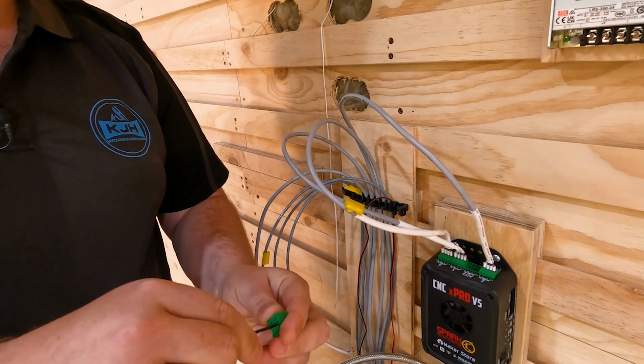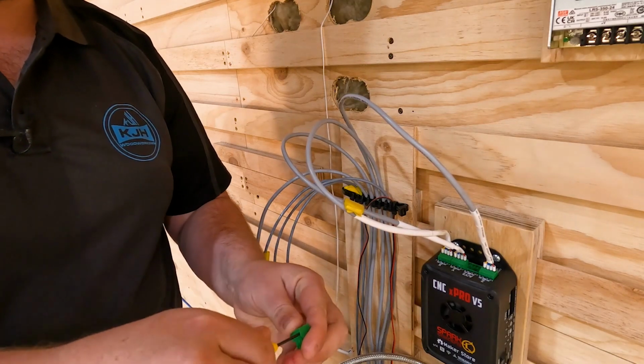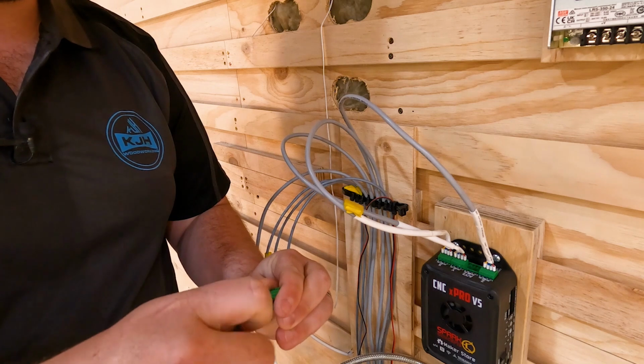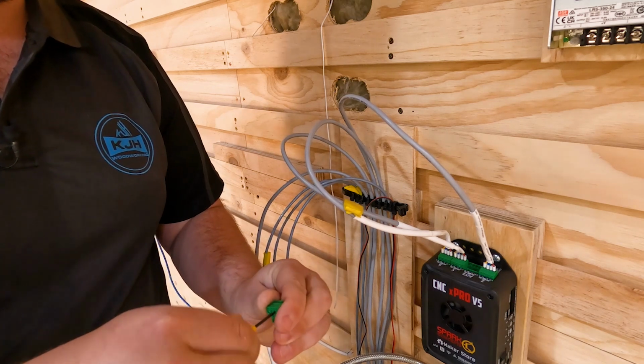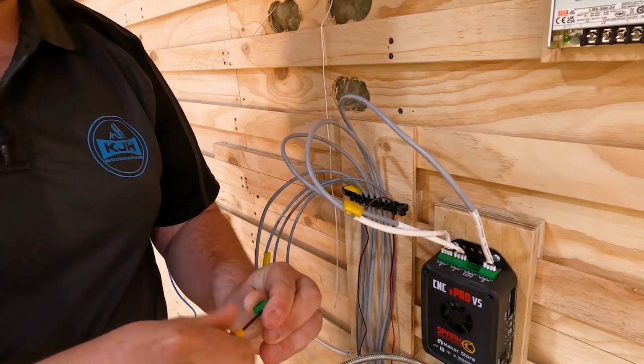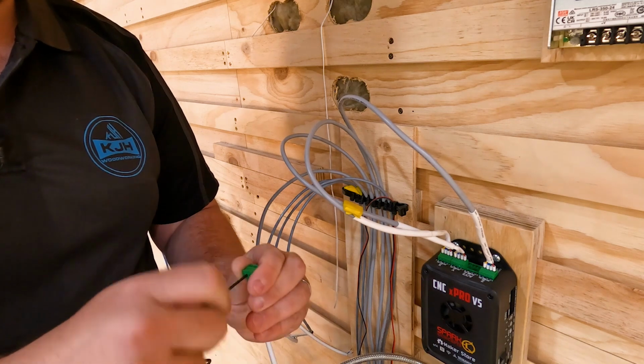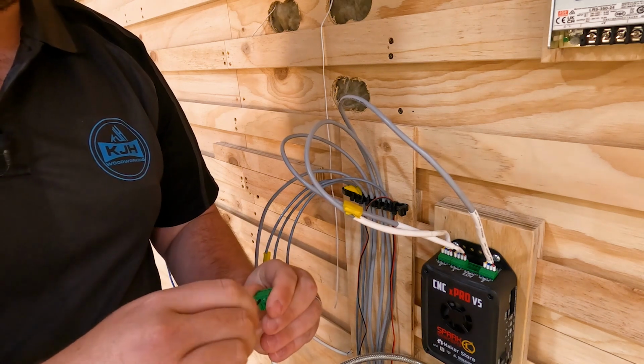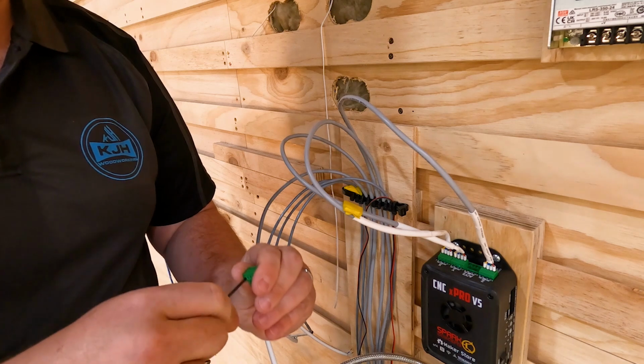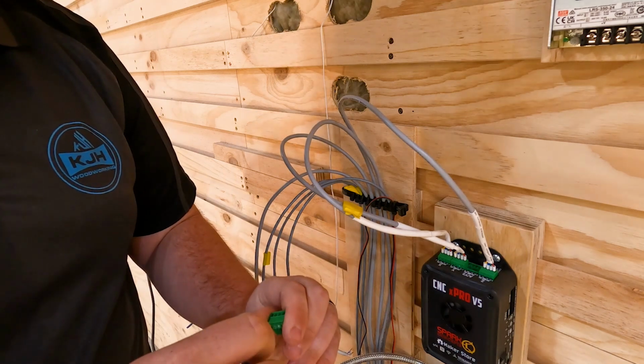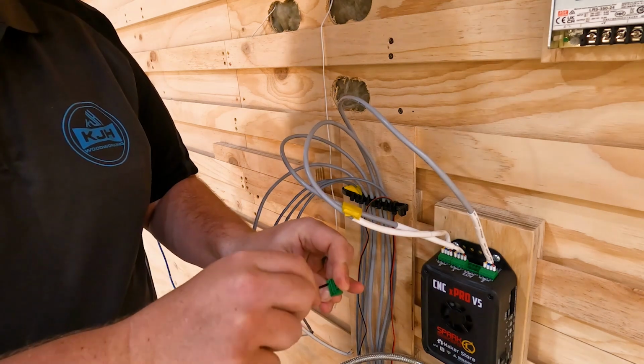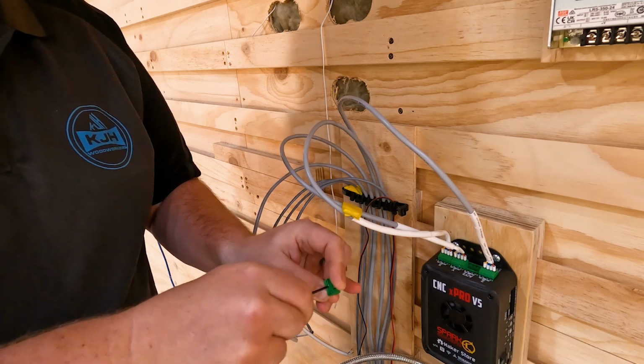For Y2, you need to reverse the colors at one end. I like to reverse it at the controller end, because then it's easy for maintenance if I've got to swap anything, since that's where everything terminates. So everything is identical down at the machine end, but at the controller end we swap this around - it'll be yellow, blue, green, red on this point.